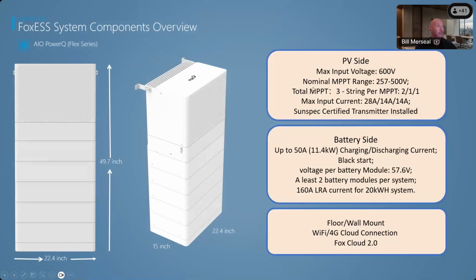From that perspective, our max input voltage — if you understand batteries, or if you've used something like Solar Edge, SolarX, what they call low voltage systems — these are high voltage systems, about 600 volts on these battery systems. That means the amperage is way less, our average operating amperage is between 50 and 60 amps, so you have to use less thick wiring, making your wiring a lot easier.